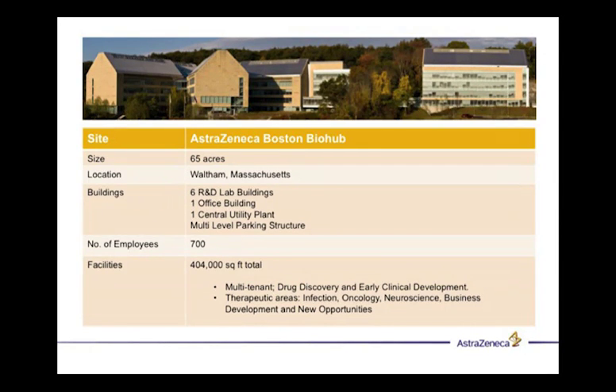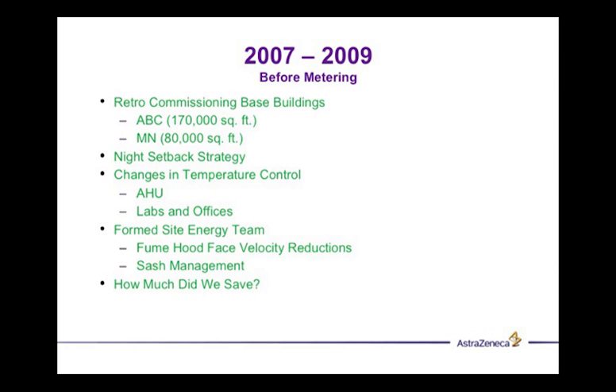About 400,000 square feet. So we started dabbling into energy reduction prior to this measure. In 2007-2009, while we were building the D&E building, the director decided he wanted to lower the cost of energy before those buildings came online, so we didn't have to increase the budget. Buildings A, B, and C at 170,000 square feet, and M&N at 80,000. We incorporated night setback strategies, changes in air temperature control, and changes in the labs and offices.